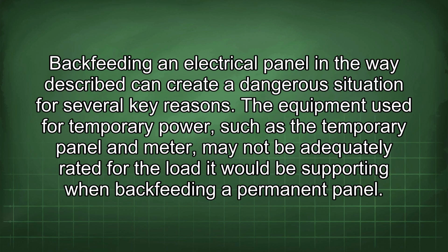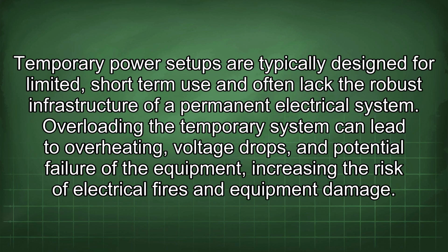Backfeeding an electrical panel in the way described can create a dangerous situation for several key reasons. The equipment used for temporary power, such as the temporary panel and meter, may not be adequately rated for the load it would be supporting when backfeeding a permanent panel. Temporary power setups are typically designed for limited, short-term use and often lack the robust infrastructure of a permanent electrical system. Overloading the temporary system can lead to overheating, voltage drops, and potential failure of the equipment, increasing the risk of electrical fires and equipment damage.